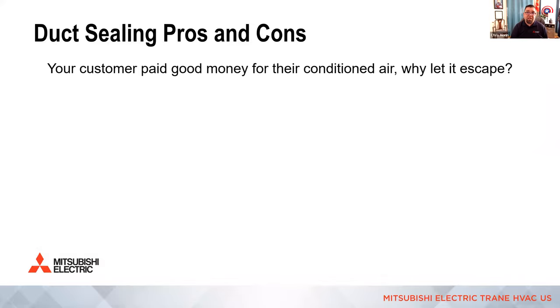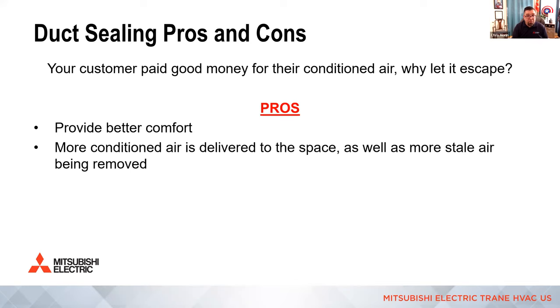Of course, just because it's not sealed doesn't mean you should seal it. You have to measure static pressure, right? So there are some obvious pros to duct sealing. Providing better comfort, more conditioned air is delivered to the space, right?